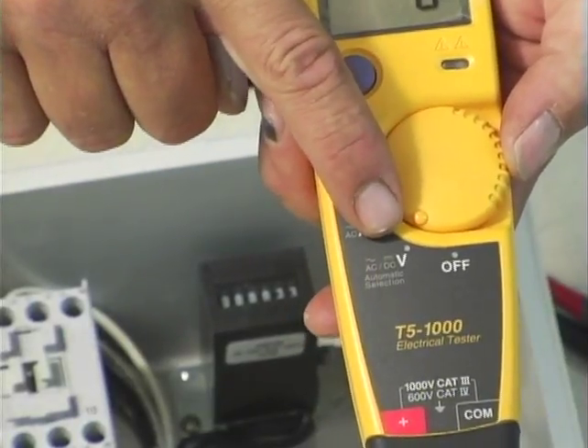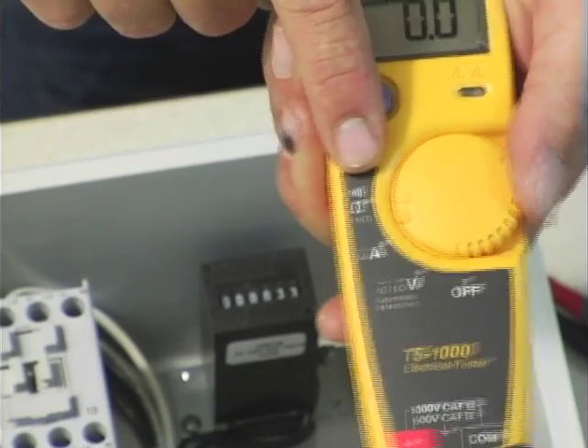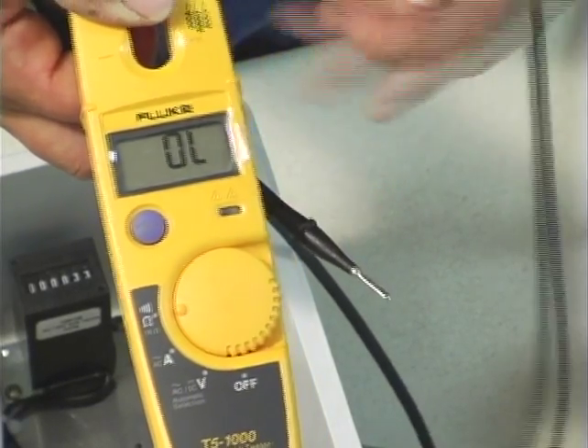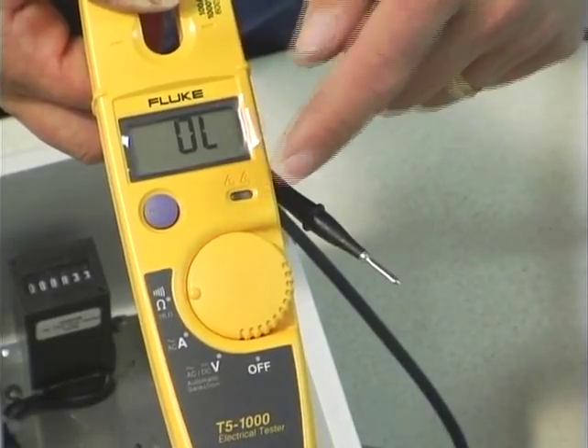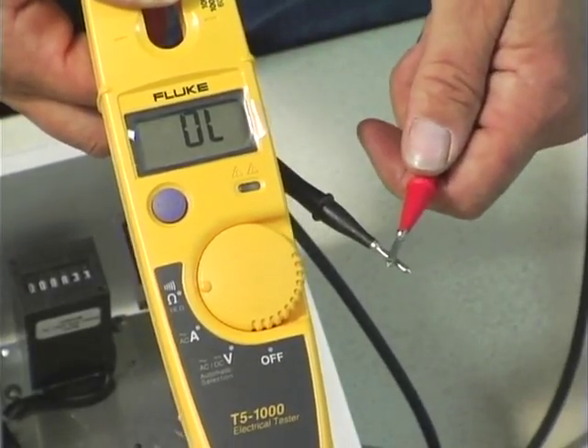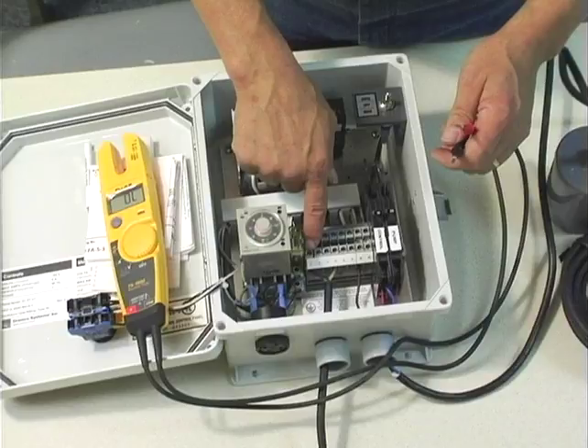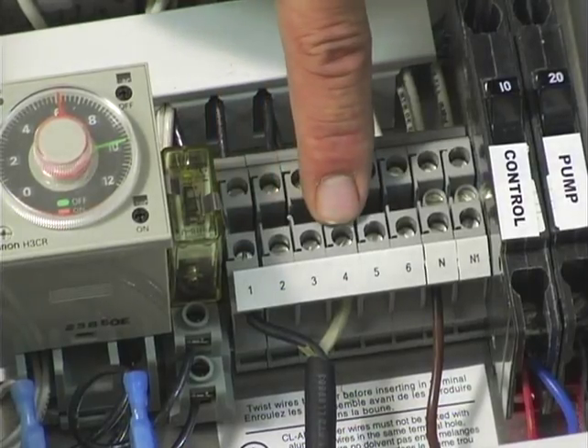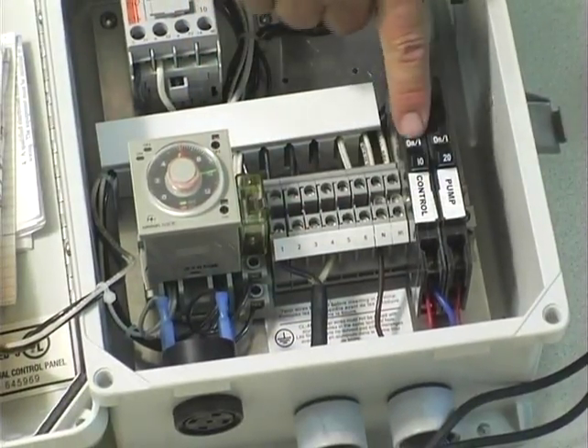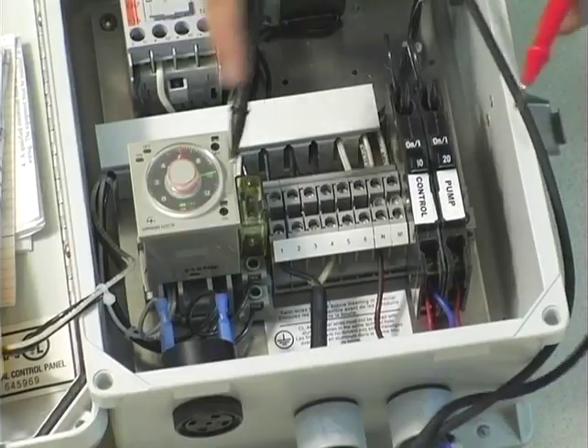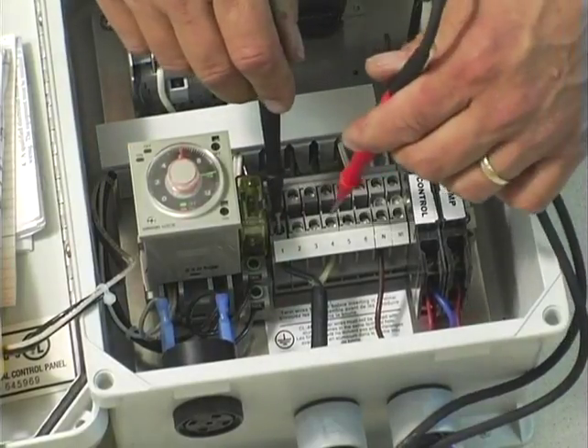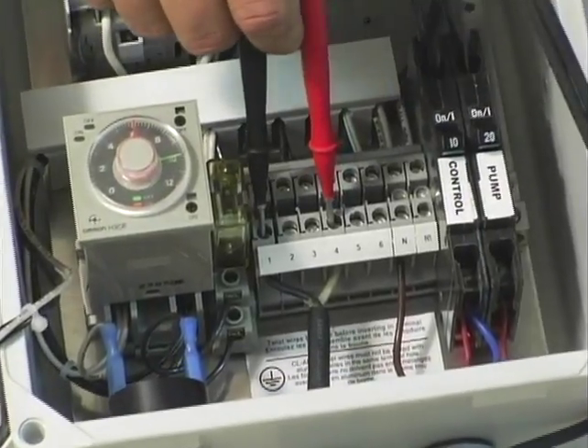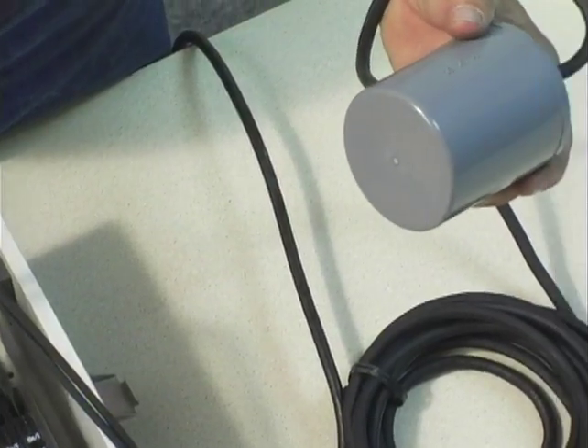Now you're not going to do this in the voltage range, you're going to move it up to the continuity range, which means when you have a closed circuit, which is how we're going to test the float switches, the meter will have a continuous beeping sound. With this particular control panel, our float switch is going to be connected to number 1 and number 4 for our timer on-off. Now what we're going to do is turn off our control and pump voltage. We're going to take our probe from number 1 to number 4, and with the float in the up position or the go position, we should get a continuity reading.